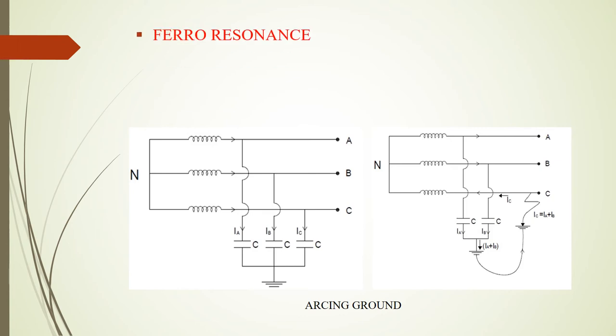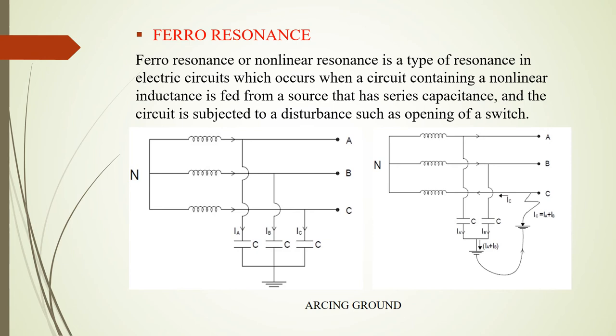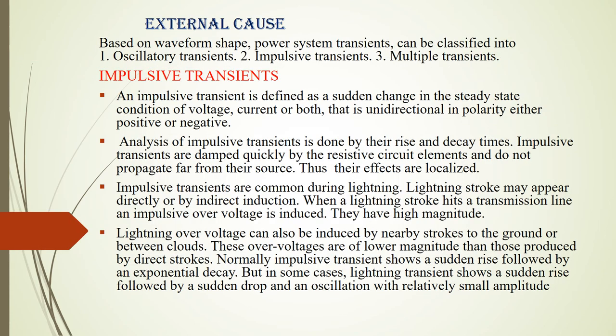Finally, we come to ferro resonance. In a linear resonance circuit, the L and C values are fixed and resonance depends on frequency. However, ferro resonance involves a non-linear inductor where the reactance not only depends on frequency but also on the magnetic flux in the core material. This gives rise to a resonance condition where the current becomes very high. Ferro resonance is a non-linear type of resonance in an electrical circuit which occurs when the circuit contains a non-linear inductance — similar to an RLC series circuit but with non-linear inductance.